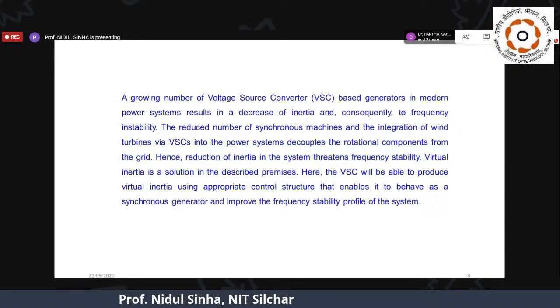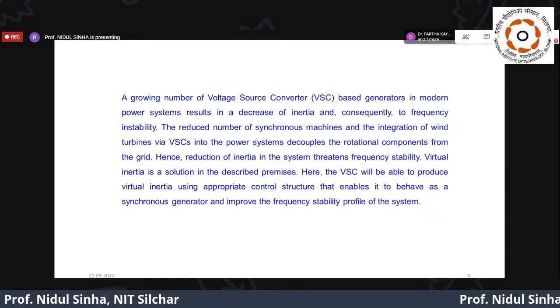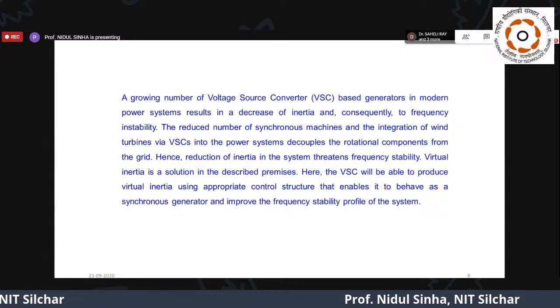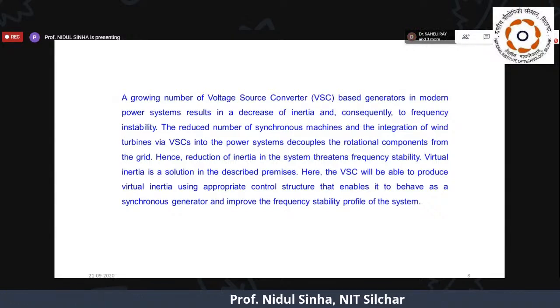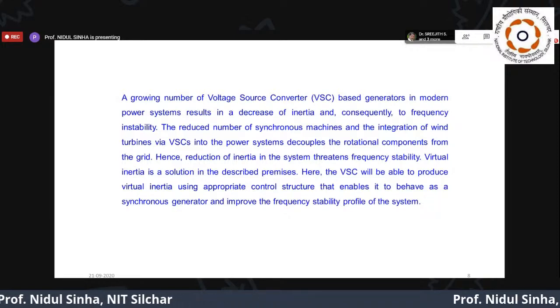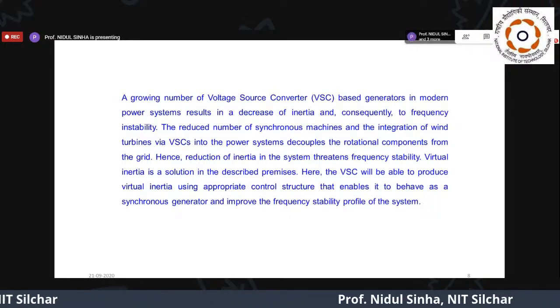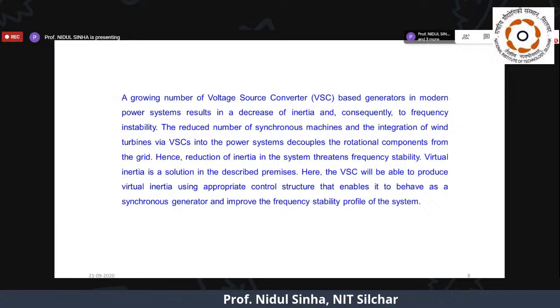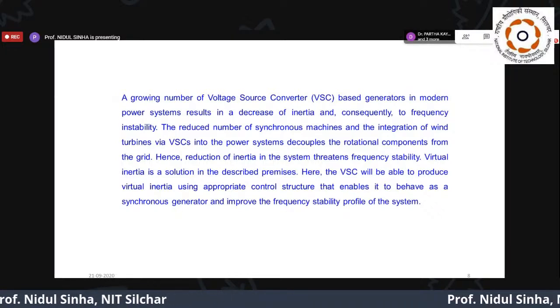Why decrease of inertia? Because now the rest of the system doesn't see what is happening to the generator. It is seeing only up to what is producing the AC. Who is that? The converter, the VSC, which is used for that. It's a power electronic device, and it's very fast.